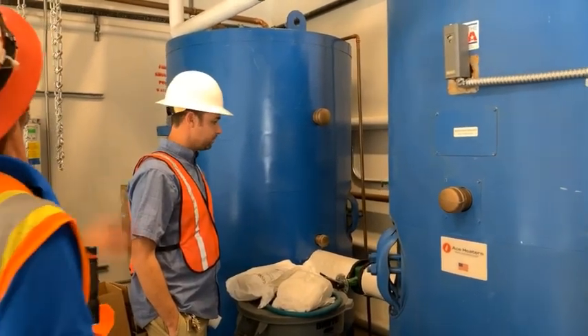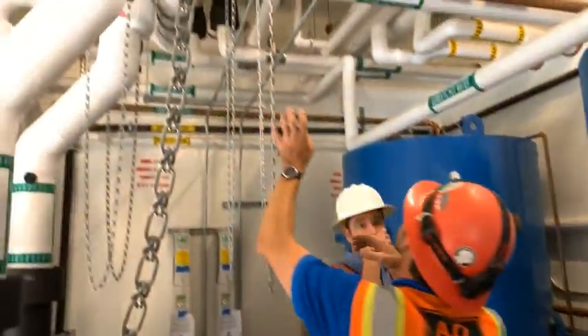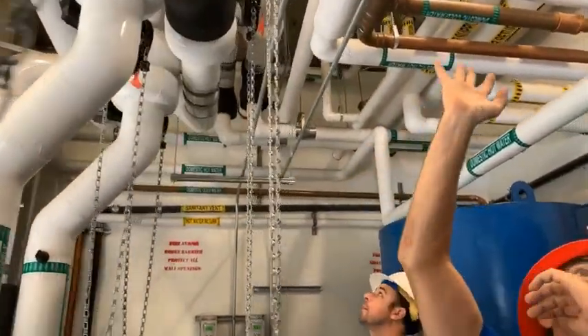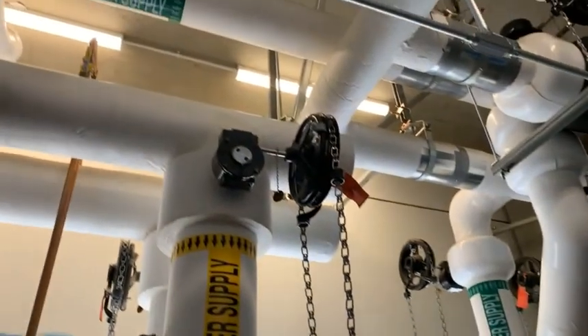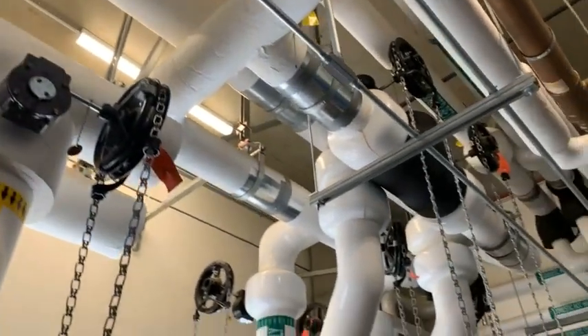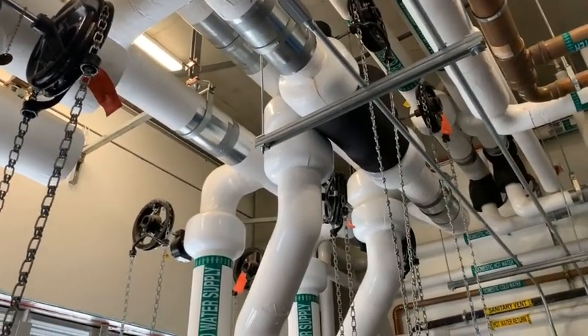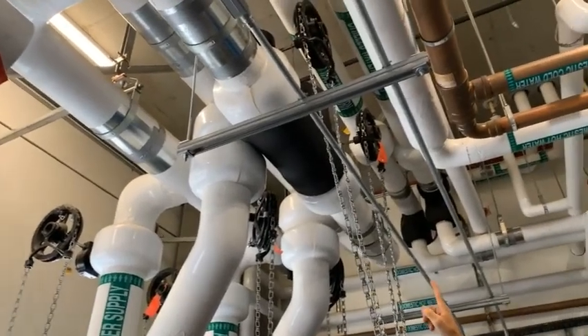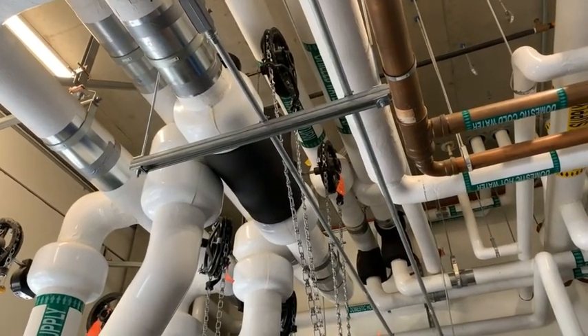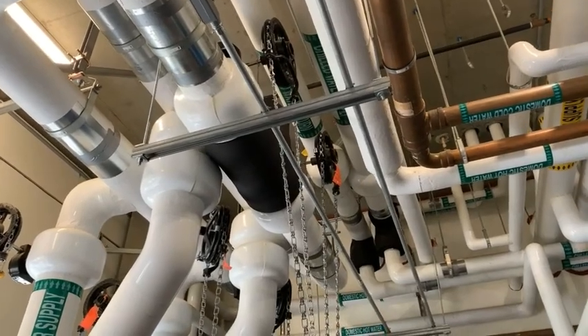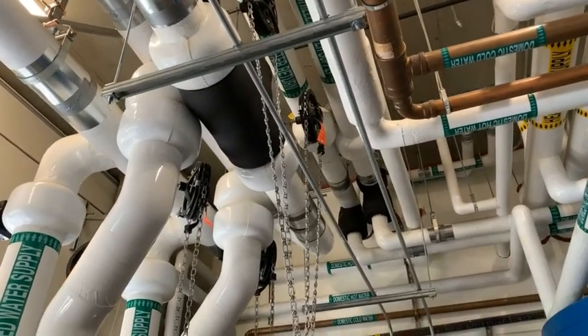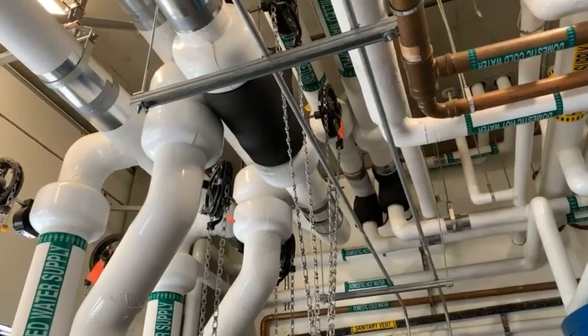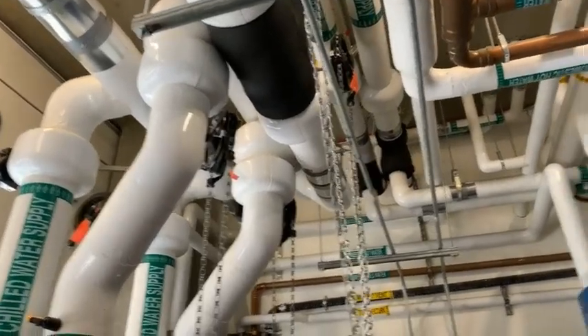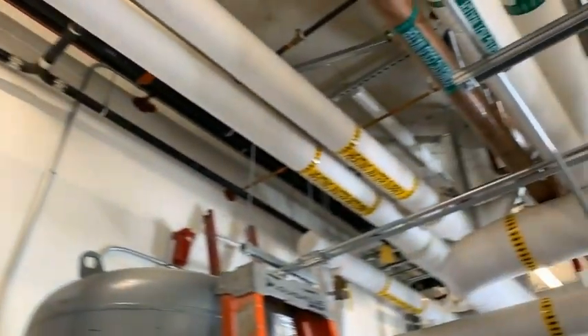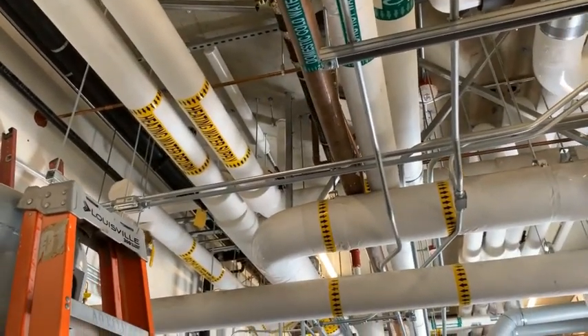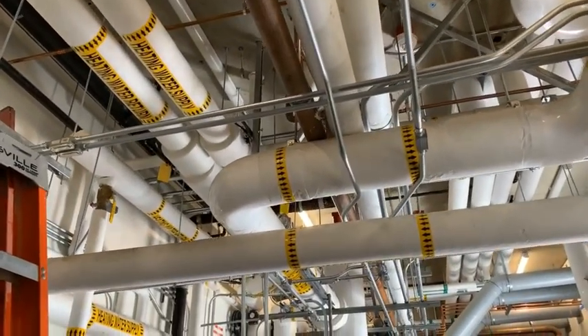In here, that's what I got. Our shutoff valves to isolate the 2 sides are going to be up above us. Let me start with this one right here. This is our bypass chilled water valve with the check valve in between. So with no pump running, the water's going to be flowing through this line to bypass the pumps. And then the heating hot water shutoff valves are over here for the segment of the building behind us. Segment 1. Chilled water valves.